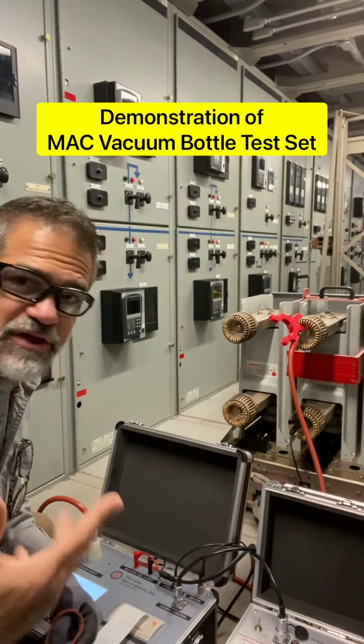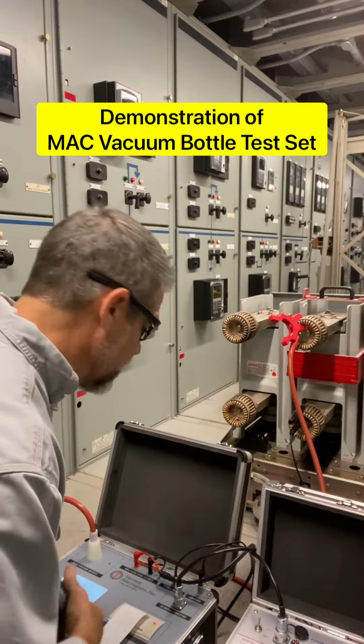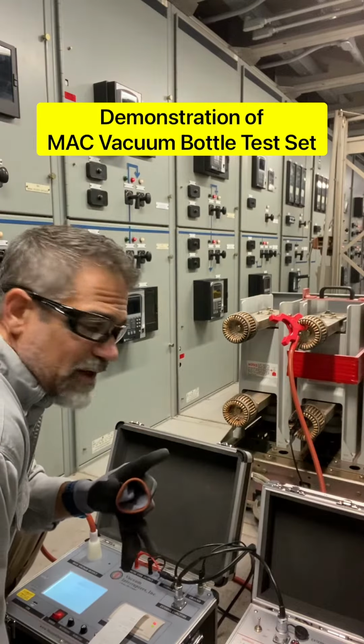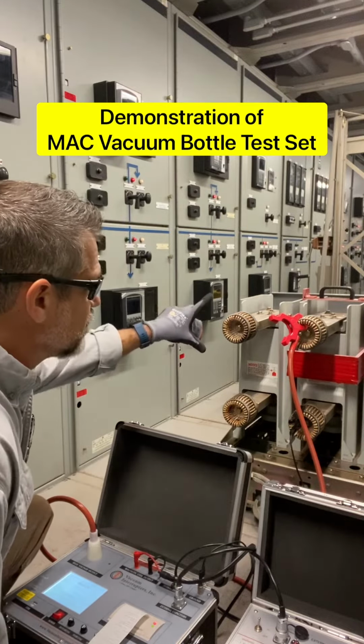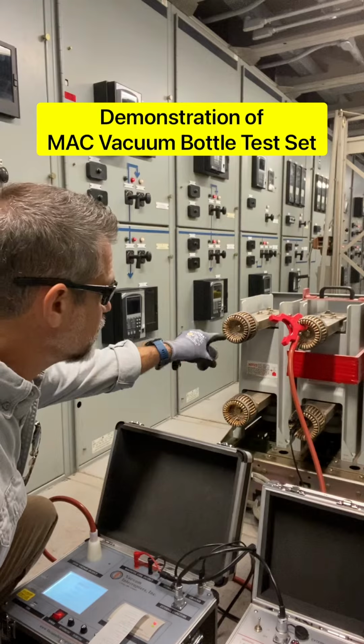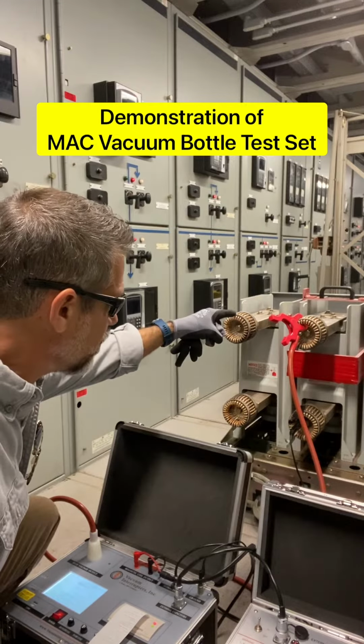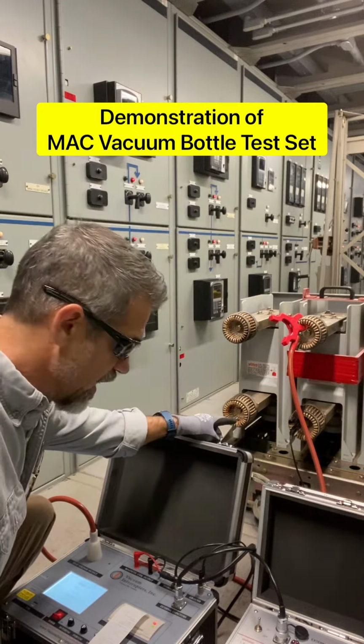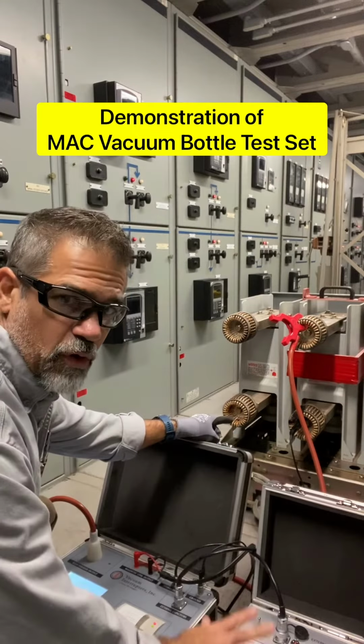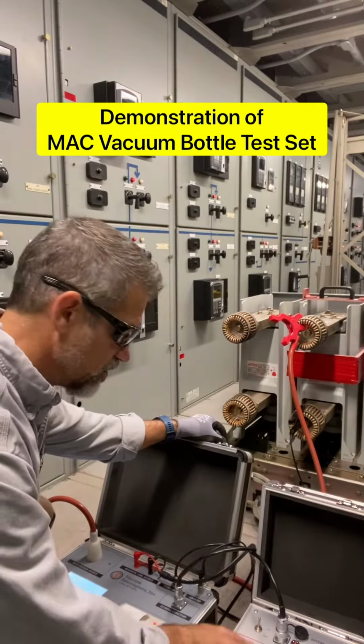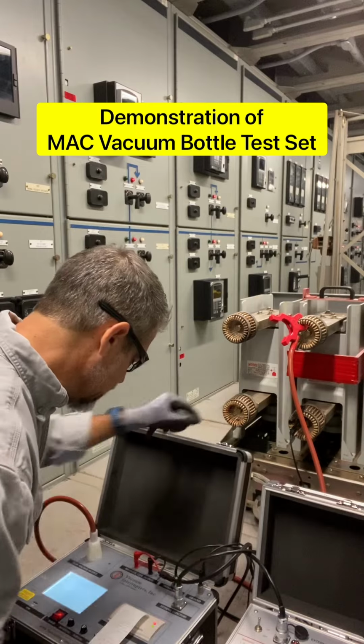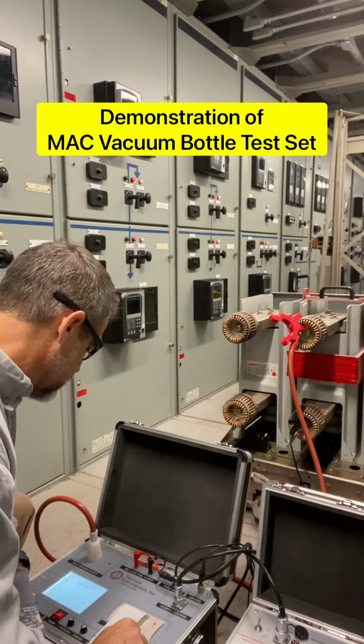All right, today we're doing a demonstration for my team behind me here on how to use the MAC test set. We've already made our connections. We've got a rigid coil around the phase here, a high voltage lead on the top of the pole, and a return lead on the bottom. Because we're using the rigid coil, we've got to use the capacitor, so we've already got that connected. Everything's ready to go, and we're just going to walk through the setup here.